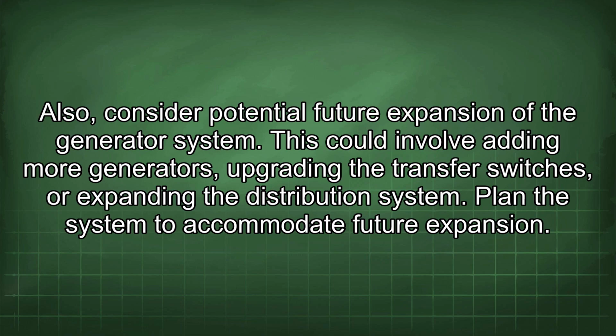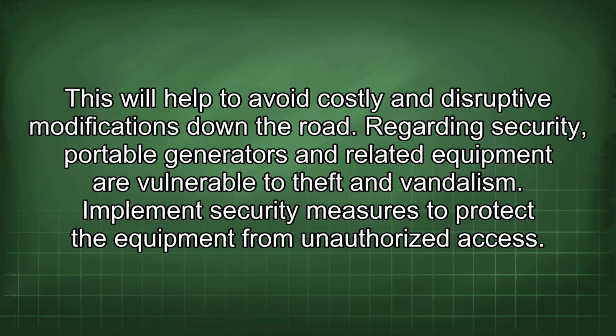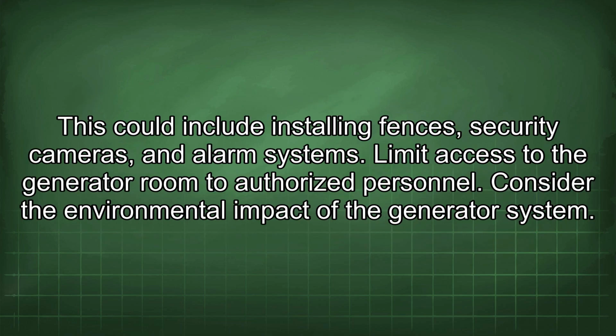Also, consider potential future expansion of the generator system. This could involve adding more generators, upgrading the transfer switches, or expanding the distribution system. Plan the system to accommodate future expansion. This will help to avoid costly and disruptive modifications down the road. Regarding security, portable generators and related equipment are vulnerable to theft and vandalism. Implement security measures to protect the equipment from unauthorized access. This could include installing fences, security cameras, and alarm systems. Limit access to the generator room to authorized personnel.